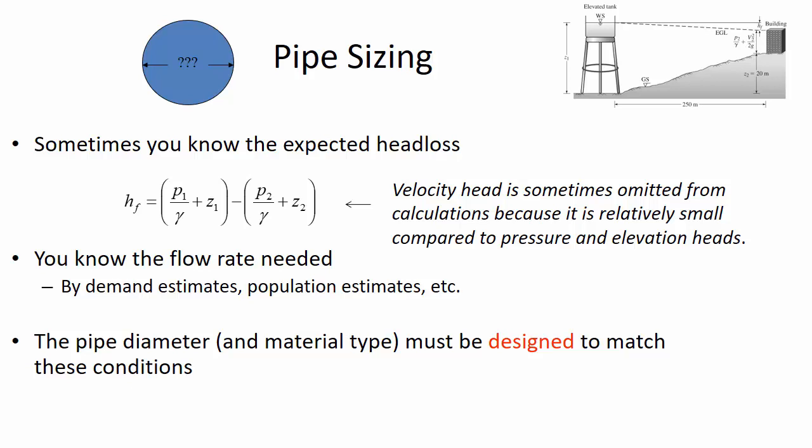And it's especially true because velocity is squared and pipe diameter is in the denominator. So a small D is going to be driving up the velocity, and then it's also a small number in the denominator, so it's going to amplify the effect. So this question is, how big does the pipe need to be? We're balancing competing factors.